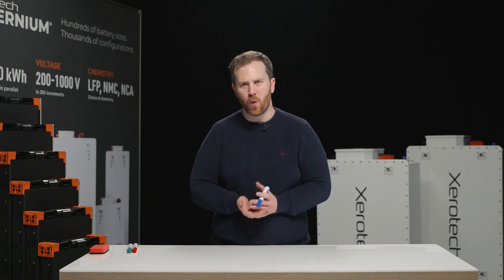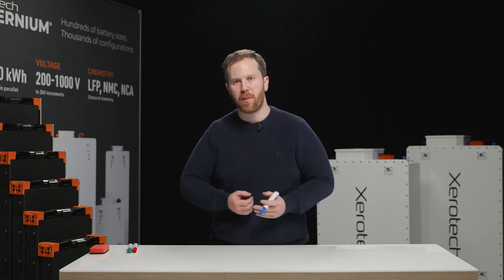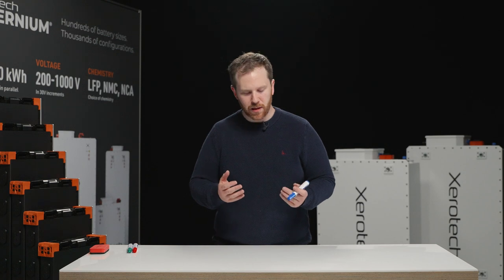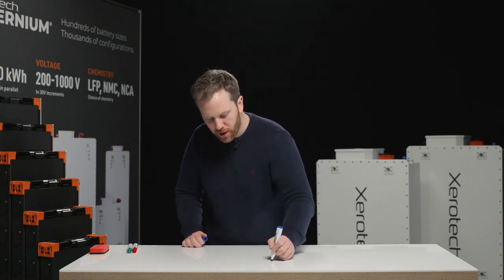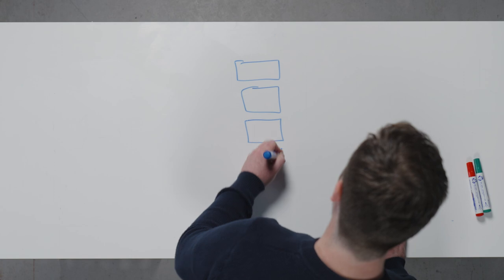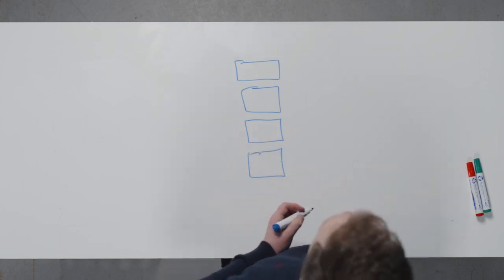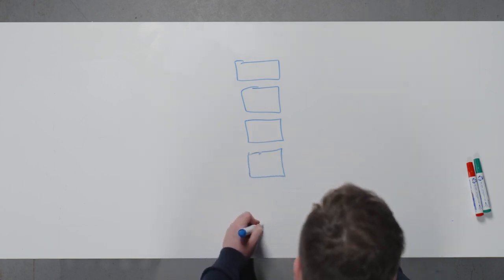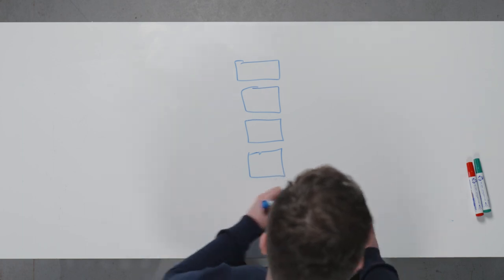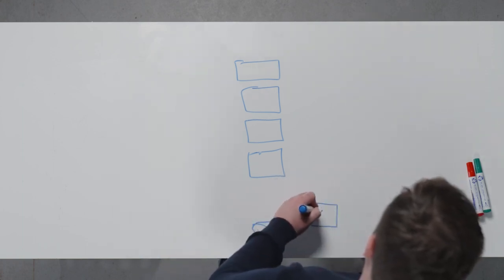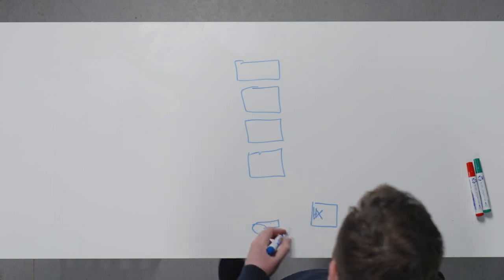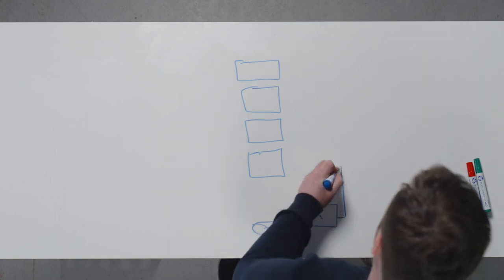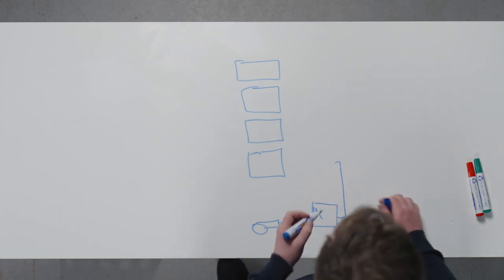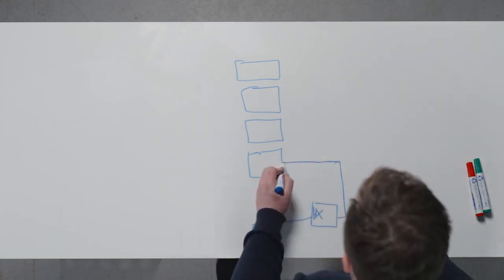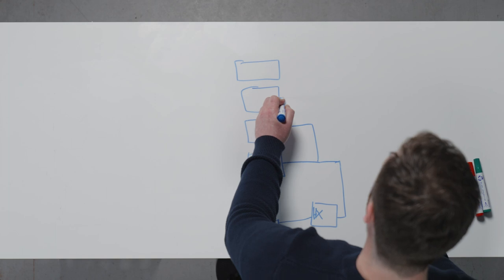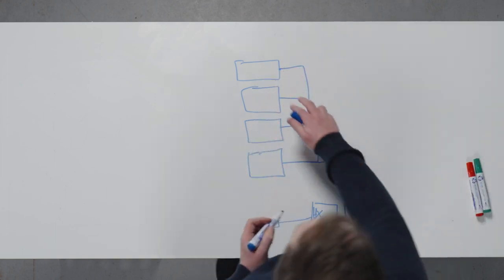So we're just going to talk about the one unique case now where a lot of complexity can arise, and that's with multi-pack installations. So we've put in our ideal system with the battery pack before the pump, but things get a little bit trickier when you've got multiple packs in parallel. So we're going to go back to our original system, a pump. We're going to put in our heat exchanger. The pump flows through the heat exchanger, goes into some sort of distribution manifold. So that's basically something that joins all these packs together. And you'll notice that we've put the packs in parallel.